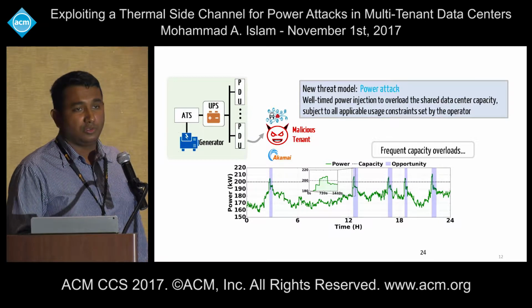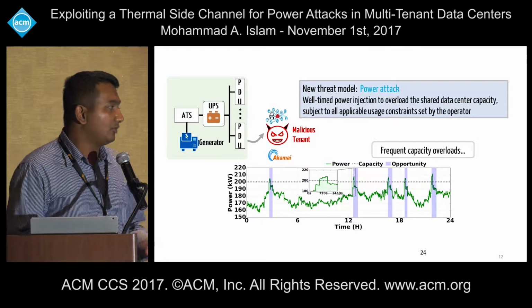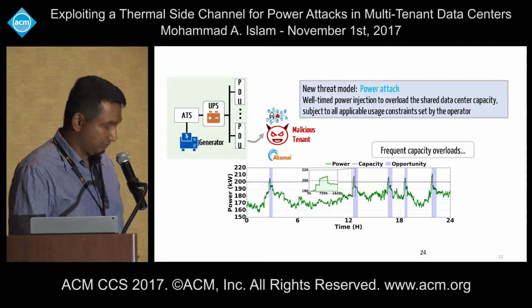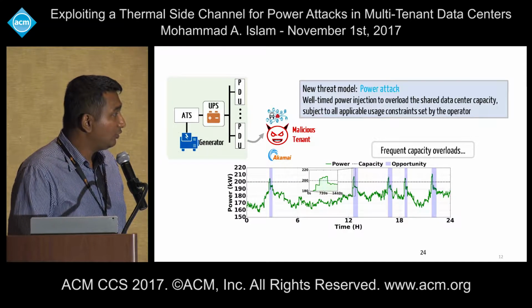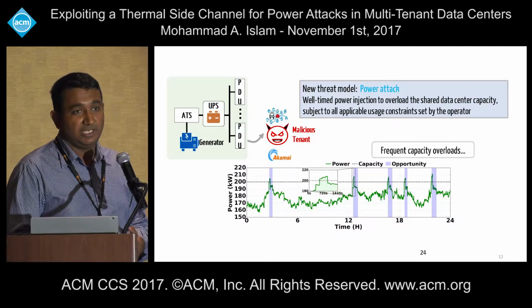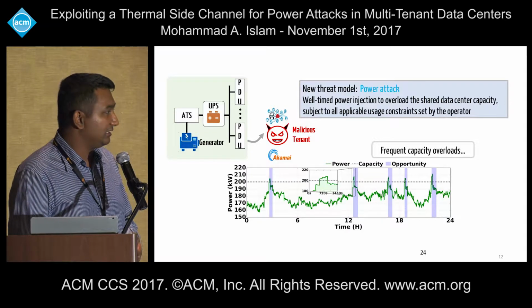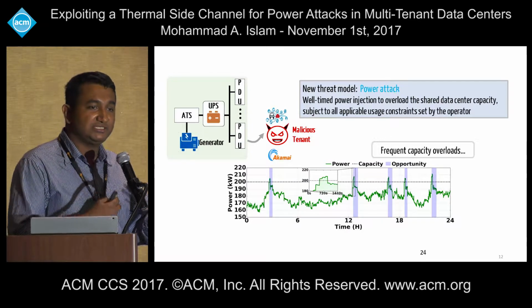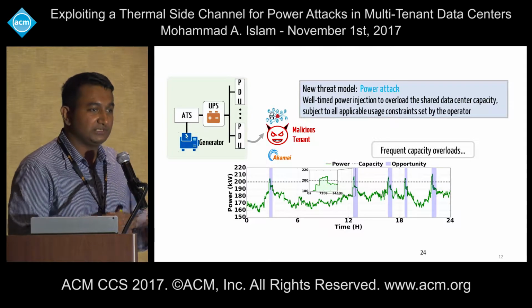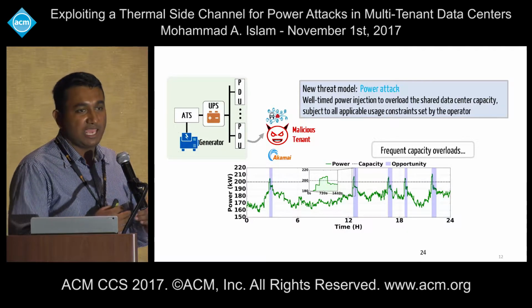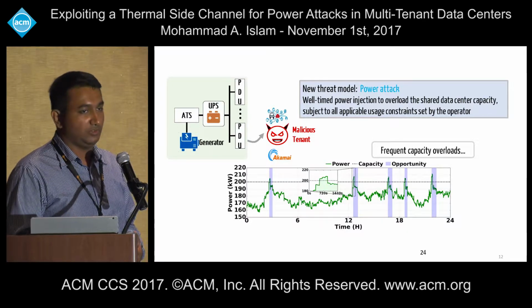But this is only true if the tenants behave normally. There are some times when the power goes really close to the capacity. And if there is a malicious tenant in the data center, it can actually increase its power at those moments and push the power above the capacity, creating a capacity overload.